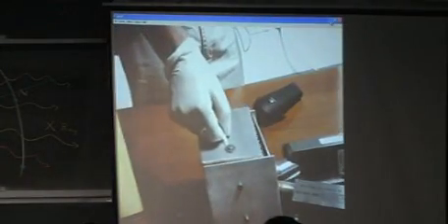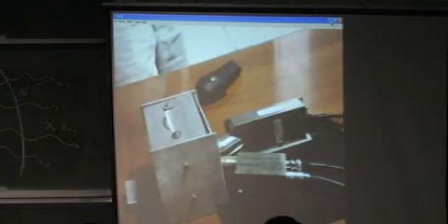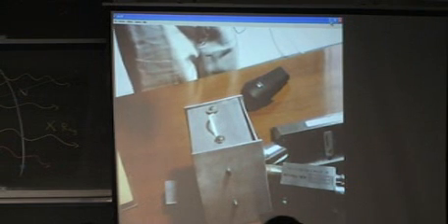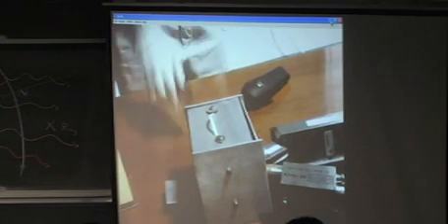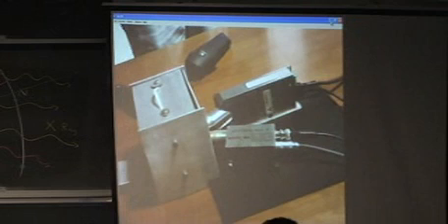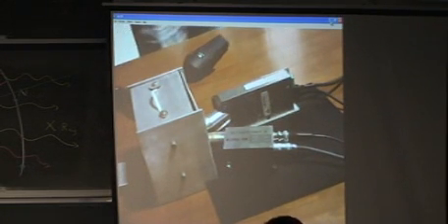The X-rays do not travel through air. They travel through inside this box, which has brass and aluminum in it. So there is minimum exposure, and I am wearing gloves because I do not want to touch the X-ray tube. It's very high voltage. If I touch the windows of the tube, it will damage. Now what I'm going to do, I'm going to run a spectrum. I'm going to turn on the X-ray tube, and I would like to see what the characteristic X-rays look like.